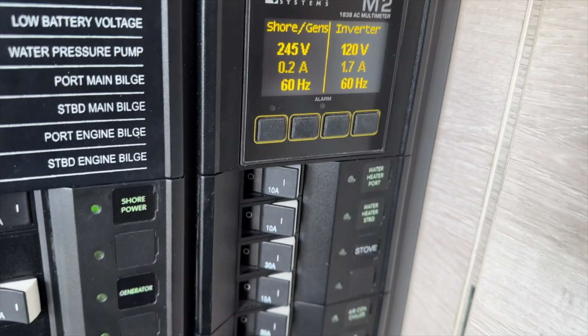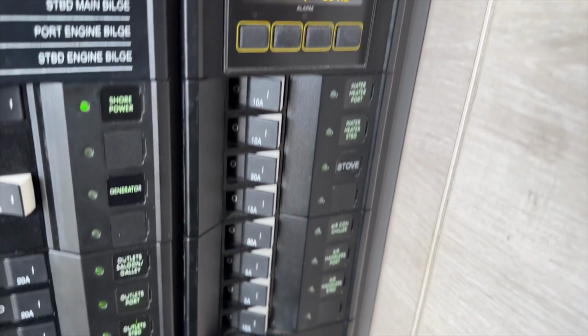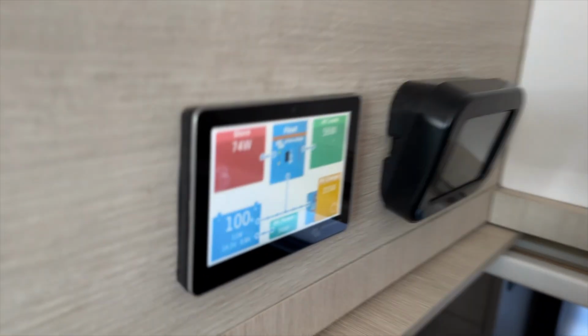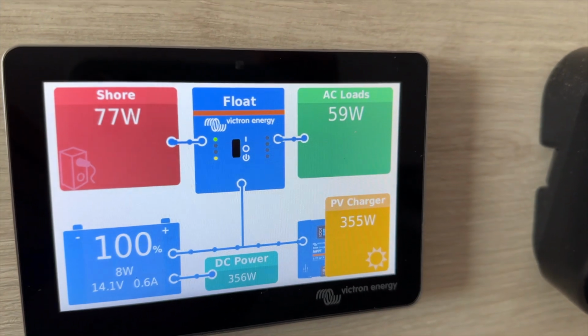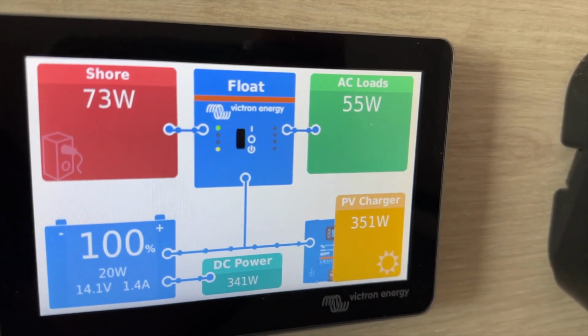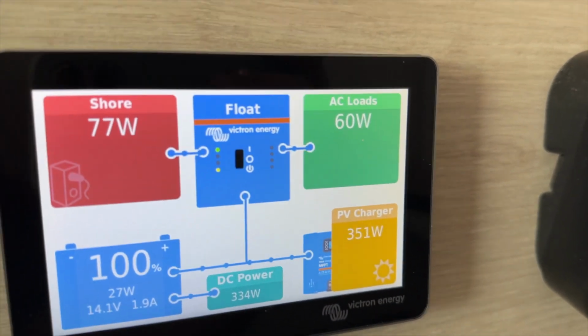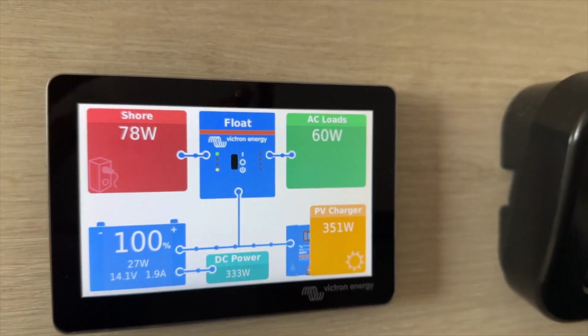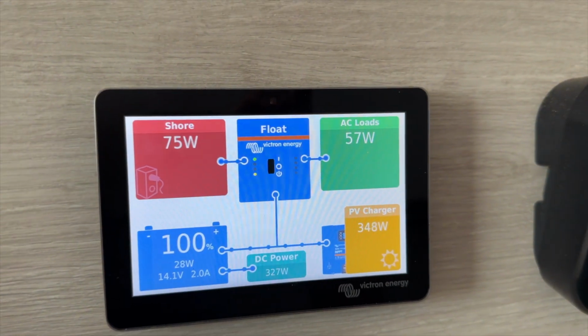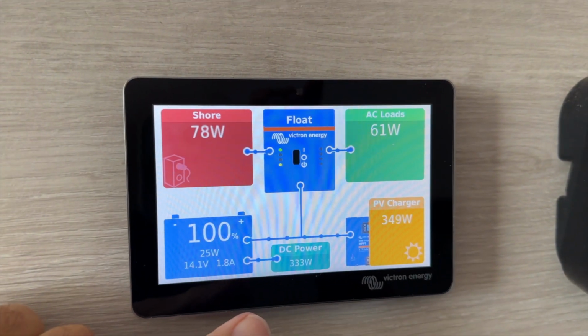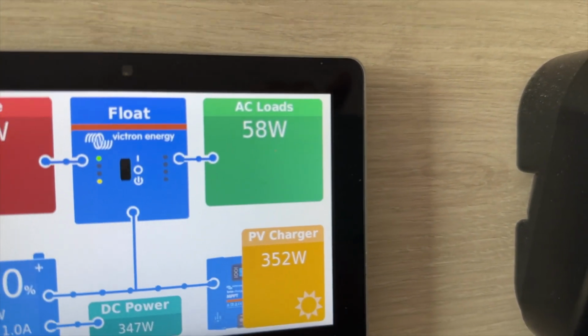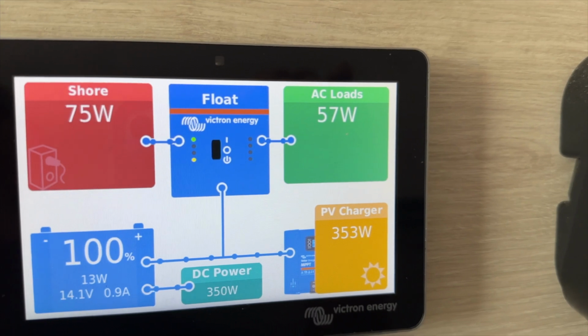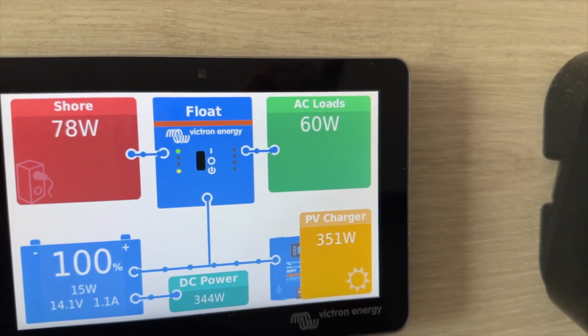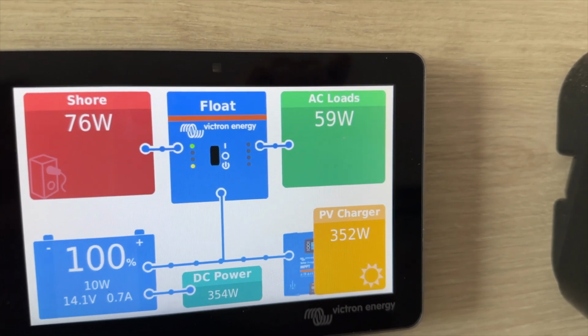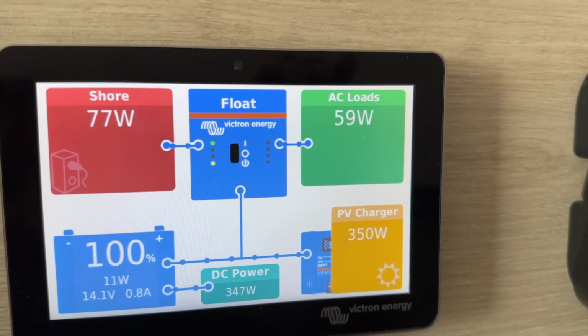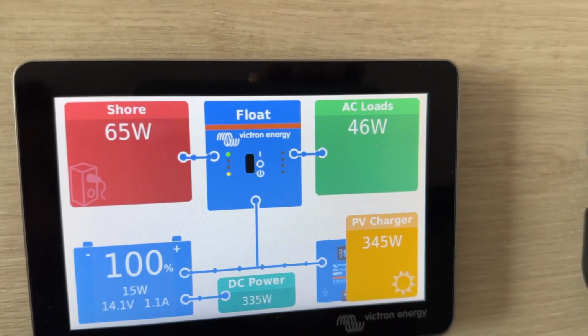Okay, so I have everything on the 230 side completely shut off, and on the AC loads, which I'm told is just the 230 or 240 side, not the 110, because all of my 110 power is inverted. So a baseline here with nothing running. I'm guessing this is just what it takes to run the Quattro. Laurent would probably know best on that, but let's call it somewhere in the neighborhood of 46, let's call it 50 to 60 watts.